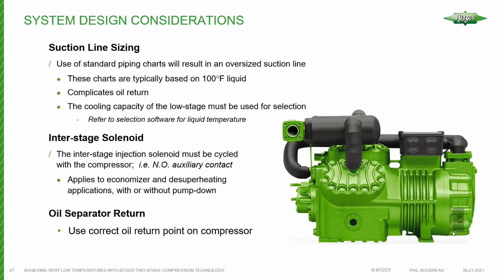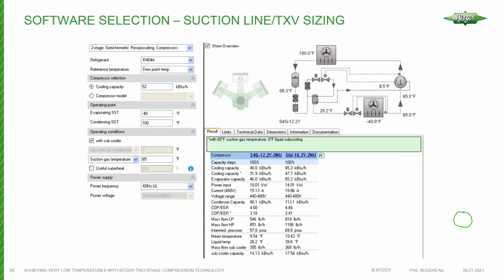The back end of the compressor on the motor barrel, basically there's a plug at, we'll call it the 7 o'clock position. If you're looking at the interstage or the motor, we'll call it the end bell at the back of the compressor, that would be where you return the oil. Of course, if it's a parallel compressor system, you're going to return this via an oil level regulator, which is installed at the sight glass position. There you go, there's the highlight. I forgot I had that there. So there's your oil return connection.